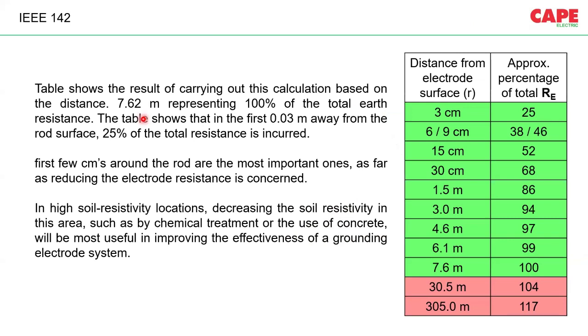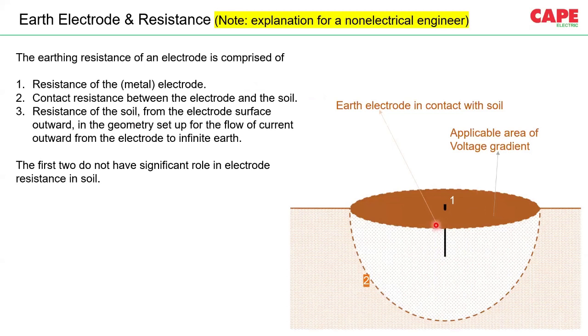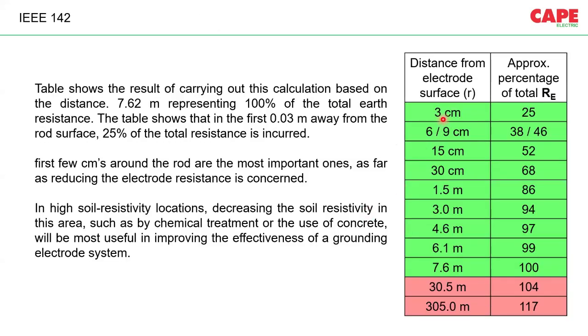Now, I'm showing you a table from IEEE 142. I don't remember the table number. You can find this IEEE table. In this particular table, they are trying to explain, or define, the influencing area as a hemisphere. Let's say, for example, this is the hemisphere and the distance from point number 1 to point number 2. And then they try to measure the resistance, the applicable resistance of that particular electrode.